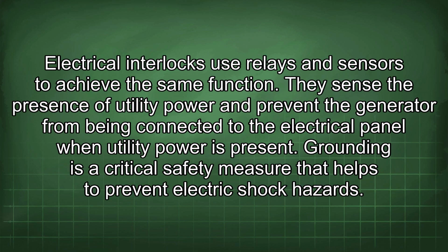Electrical interlocks use relays and sensors to achieve the same function. They sense the presence of utility power and prevent the generator from being connected to the electrical panel when utility power is present. Grounding is a critical safety measure that helps to prevent electric shock hazards.